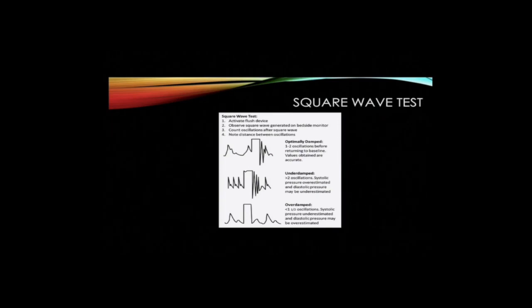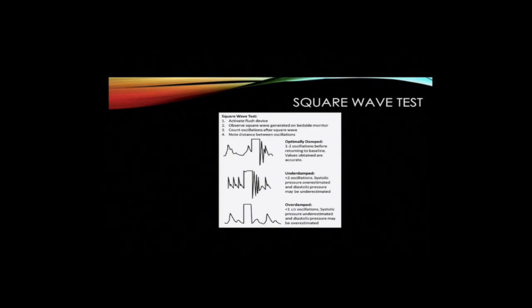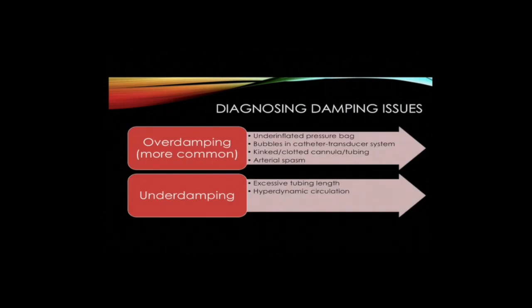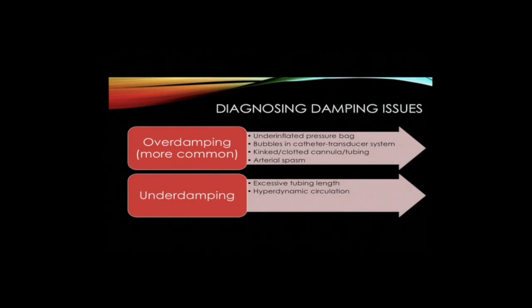A square wave test can be done to ascertain if the tracing is under or over-damped. In an optimally damped trace, there should be one to two oscillations before a return to the baseline. Common causes of over-damping include an under-inflated pressure bag, bubbles in the catheter transducer system, a kinked or clotted cannula or tubing, or arterial spasm. Common causes of under-damping include excessive tubing length and a hyperdynamic circulation.